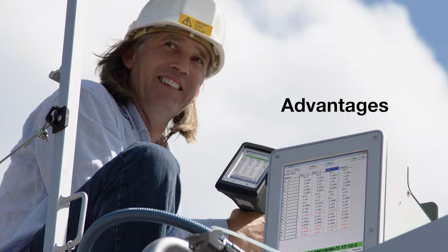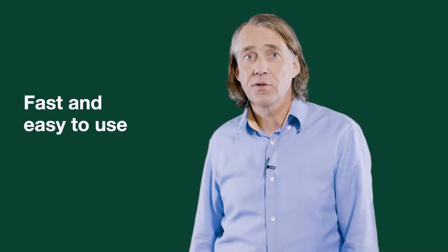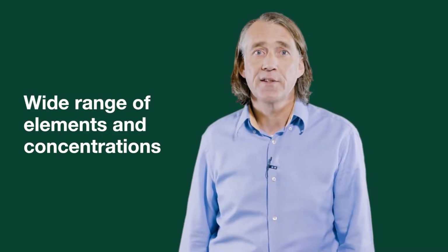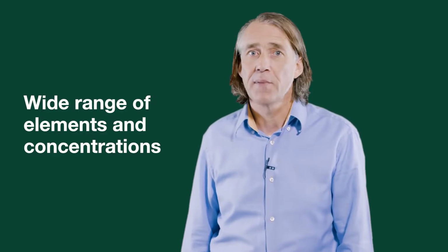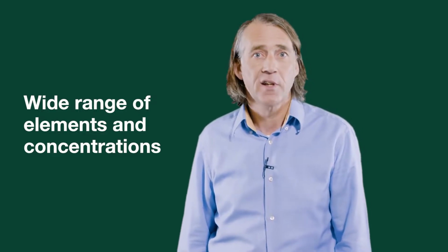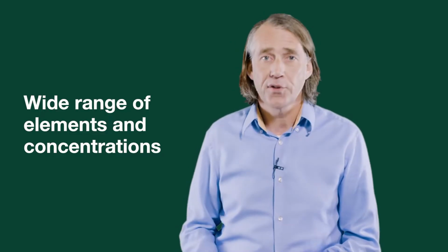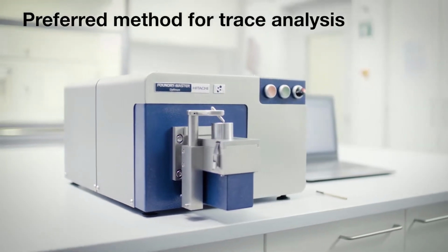Compared to other analytical techniques, OES has many advantages. It's fast and relatively easy to use. It measures a wide range of elements and concentrations in many different types of materials, including important elements such as carbon, sulfur, phosphorus, boron, and nitrogen. It's extremely accurate when measuring low levels of traces and tramp elements, and it's fairly low cost compared to other techniques. For trace analysis of metals, OES is the preferred method. OES is also currently the only method which can analyze carbon and nitrogen on site, out of the laboratory.